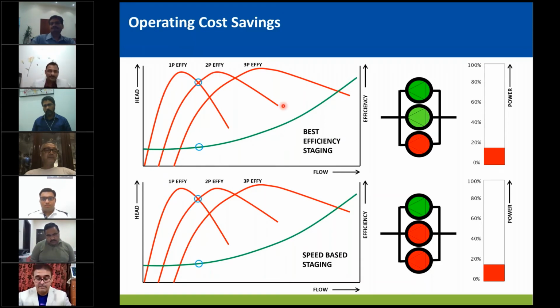So let's see what happens from this point. The speed-based staging has loaded up the first pump to approximately 90% speed, and the best efficiency staging has staged on 2 pumps, operating 2 pumps at part load, but at a high efficiency point. Now, although it's operating 2 pumps, the power consumed is less than 1 pump operating at full speed. This is one opportunity point. Let's plot that point here.